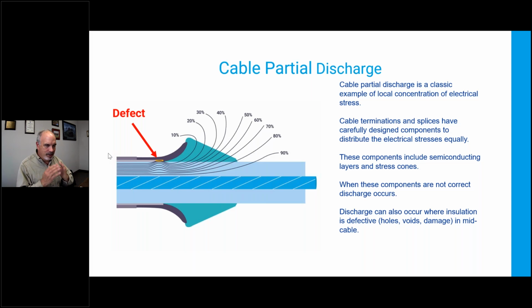Cable discharge is, like I said, very common. It's a real issue in lots of places where I have a defect, right? So I've seen workmanship issues in the field. I had a guy in a trench terminating a cable. If that isn't done right, you can get a defect, and that defect is not immediately visible. It can cause a lot of discharge. And places that have had booms in the oil industry or the offshore industry, where they're making a lot of cables in a short time, they get people that are less skilled and less trained, they tend to have more problems. It always makes sense.